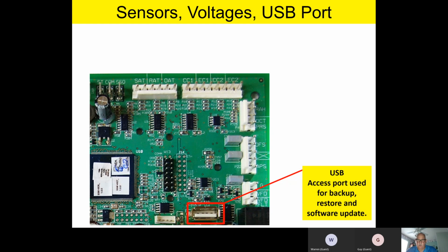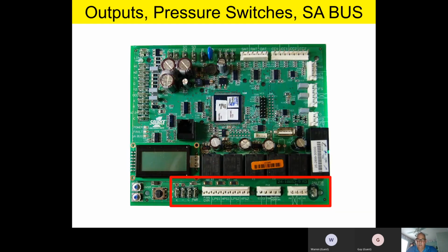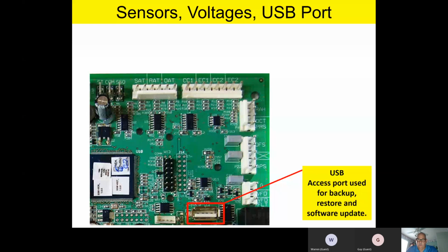Right around the corner from him is a USB port. This is going to be used to access a USB drive for backup and restore functions. And if you have software updates, you can plug that in and you can update your software. Now, team, I'm gonna recommend something, and this is again from the old tech head here. If you've got a unit, let's say it's a couple years old or a year old, whatever, and you're running on a conventional thermostat, and the unit's working fine, there is absolutely no reason to update the board.